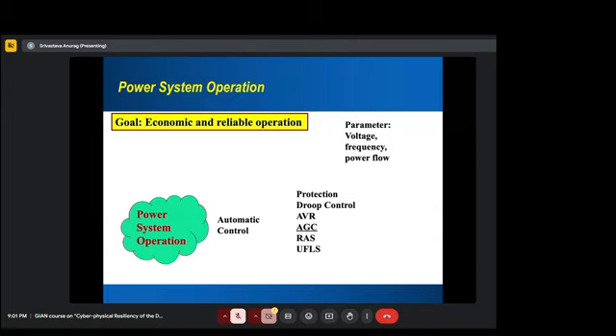Then there is the AVR, automatic voltage regulator, which is monitoring the voltage and changing basically a lot of different things. One of the things it will change is the field current in the generation plant to make the voltage control. And AGC is automatic generation control. It is looking at the real power and changing the fuel injection to increase the generation.